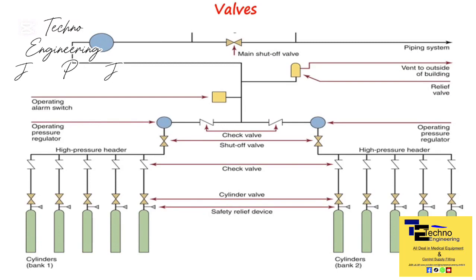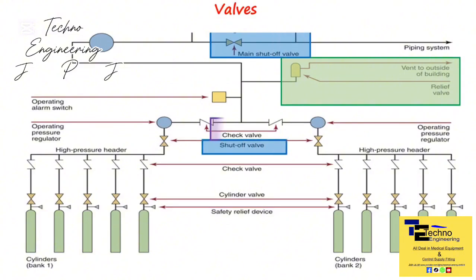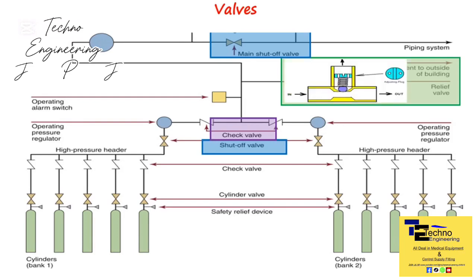Pipeline systems have valves installed at various levels, including pressure relief valves, shut-off valves, and check valves. For effective operation, each central supply system requires a pressure relief valve set 50% above normal line pressure, located between the pressure regulator and the shut-off valves, to prevent pressure buildup. The valve should close automatically when the excess pressure has been relieved.